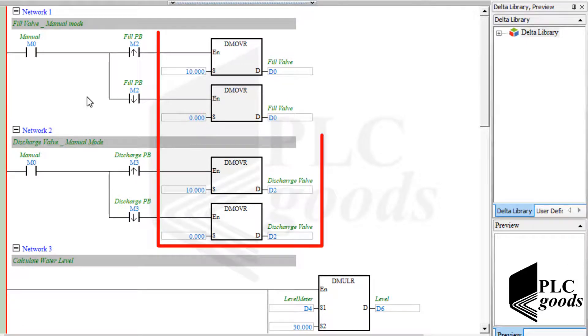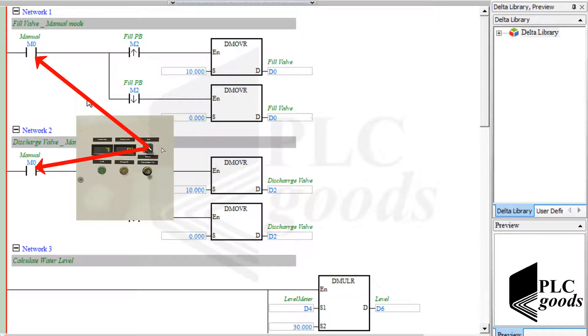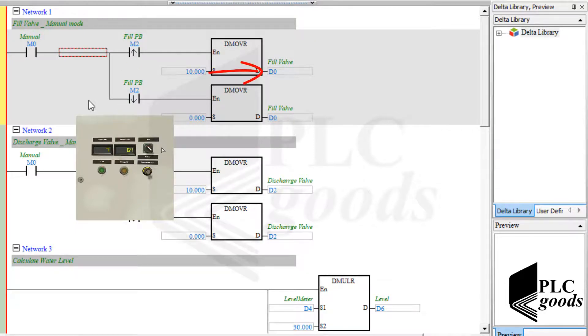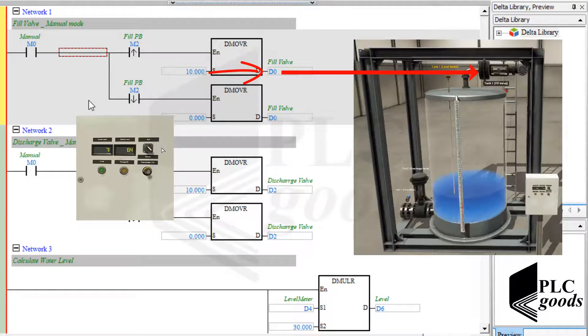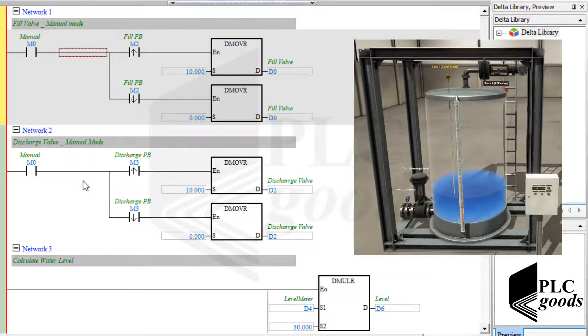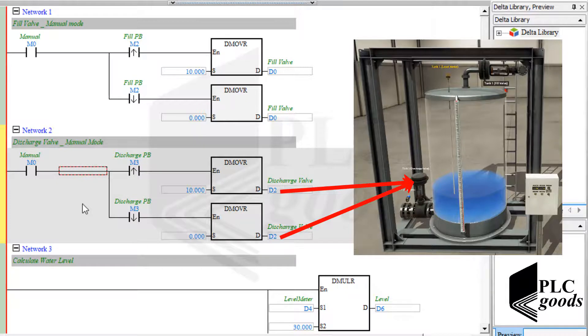The first condition to activate these move instructions is to select manual mode. The first network opens and closes the fill valve based on the first push button state. If I press it, this contact will detect its positive signal edge, and then number 10 will be moved to this memory, which is connected to the fill valve via the OPC server. If I release the first push button, this contact will detect the falling signal edge, and PLC will move number 0 to close the fill valve. The second network uses the same logic to open and close the discharge valve when manual mode is selected.